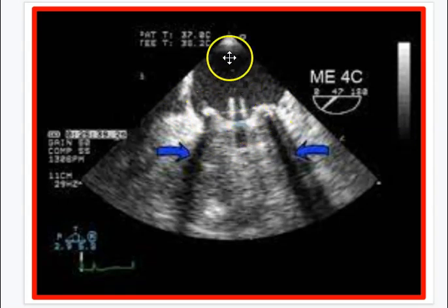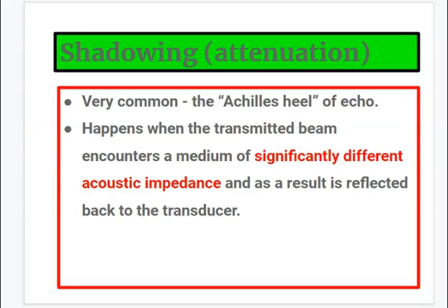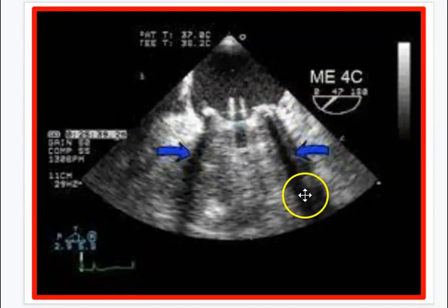We see the struts here, our beams coming in. And what's happened is you see this shadowing artifact over here. Again, we're talking about shadowing and attenuation. So we can't see anything over here. What's happening is our pulse is coming down, just hitting this metal structure, and all of our energy is just being reflected back. So we get very, very little penetration, and we can't really see down into the left ventricle. It's just being wiped out by this attenuation, if you will.